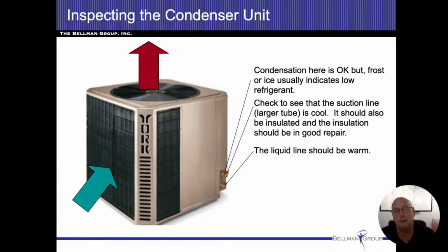On the bottom there, we see the refrigerant line connections, so the thicker line and the liquid line. We can actually put thermometers on those, and we can go ahead and figure out what the temperature difference is, or the delta on that, and that'll also tell us if the air conditioning system is working properly. But truthfully, we don't do that, all right? I was toying with the idea of doing it, but we don't. We get enough accuracy that everything's working fine just by checking the temperature drop on the inside.